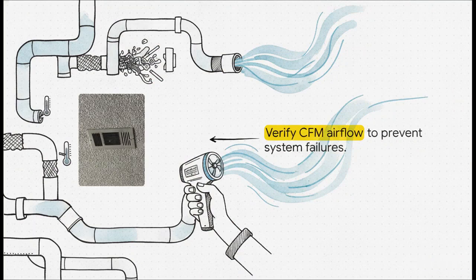And you know where a lot of technicians completely miss the mark? Right here. Airflow deficiencies, measured in cubic feet per minute or CFM, are very often the actual root cause behind weak airflow or uneven temperatures. We're talking dirty filters, blocked ducts, or closed registers causing massive systemic imbalances way before a mechanical part actually breaks. An elite professional always verifies CFM and airflow first, simply because so many major HVAC problems actually start entirely outside the mechanical equipment itself.